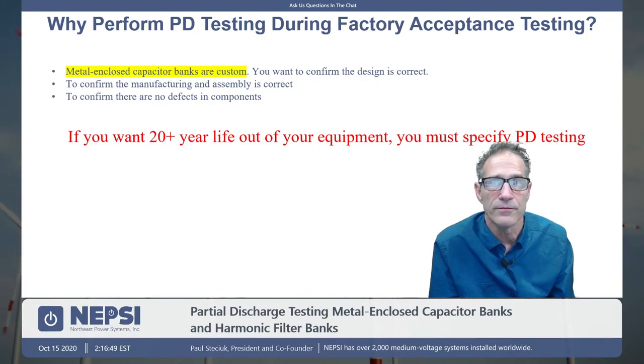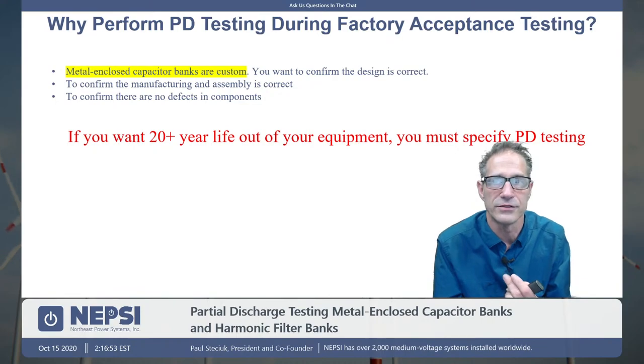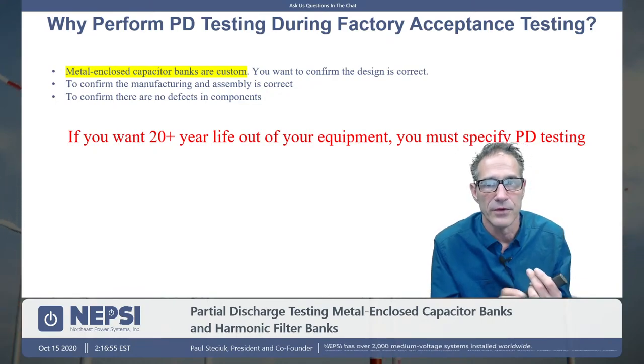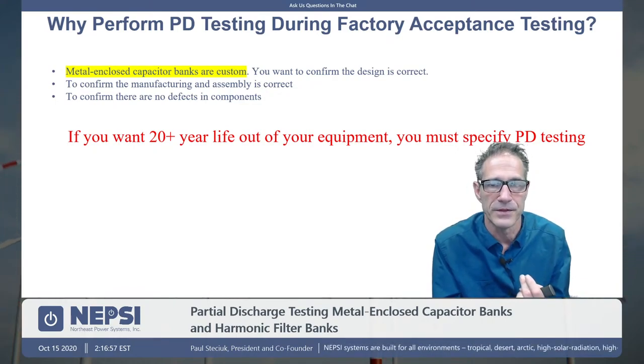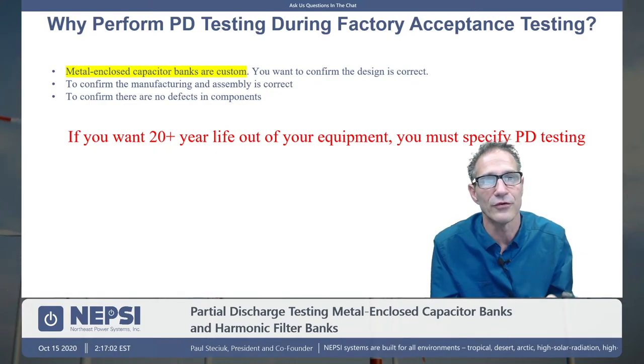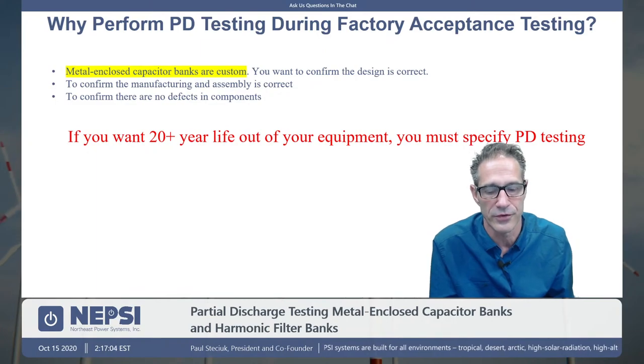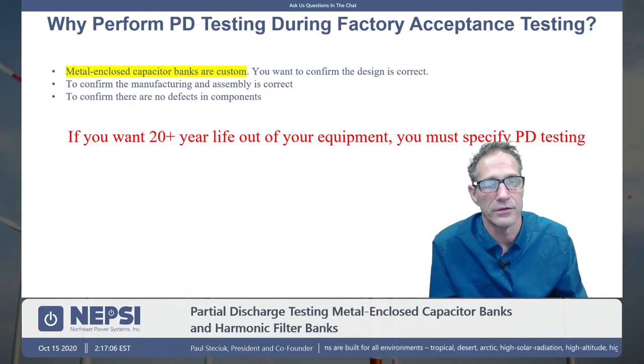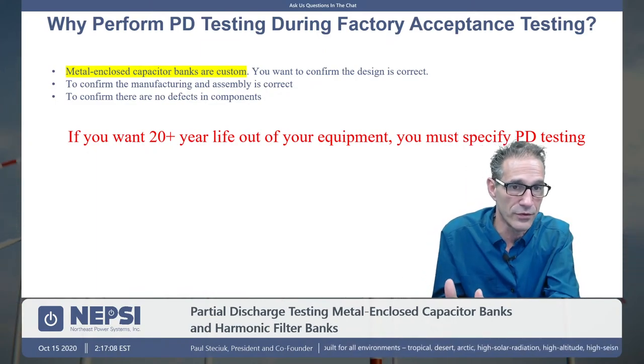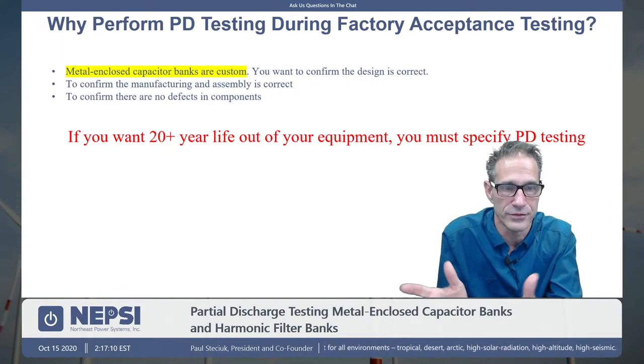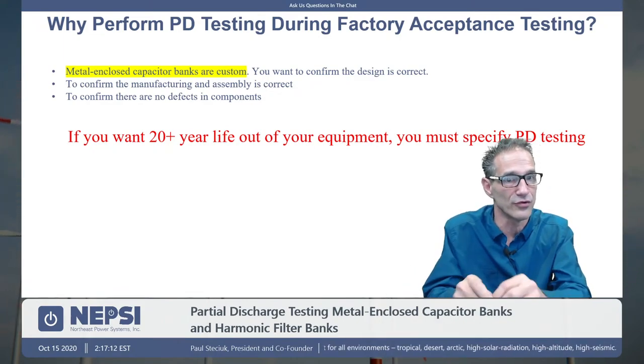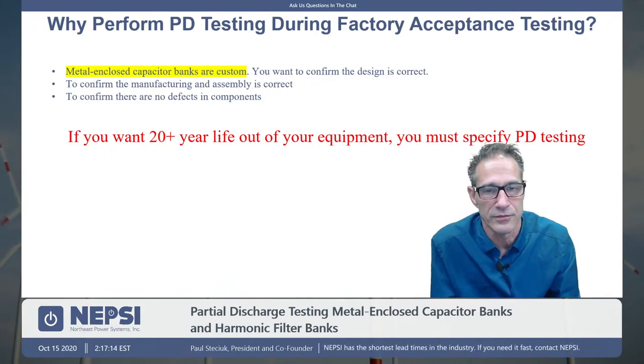So why perform partial discharge testing during factory acceptance tests? I think I've already mentioned it, but let's do it again. Metal-enclosed capacitor banks are custom, and so you want to confirm that the design is correct, but you also want to confirm that the manufacturing process is correct. We're sending equipment out to the shop. We have a bunch of people that are assembling these systems according to drawings. Did they do it correctly?